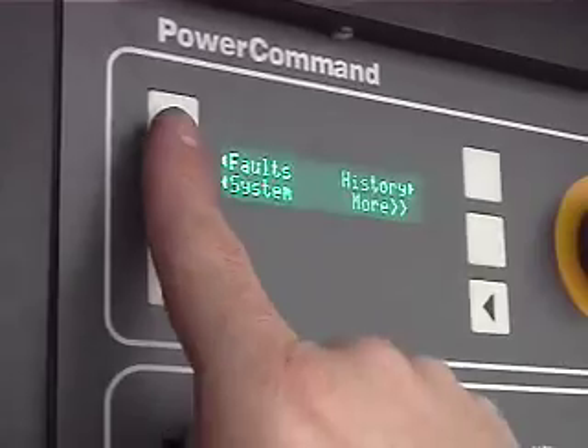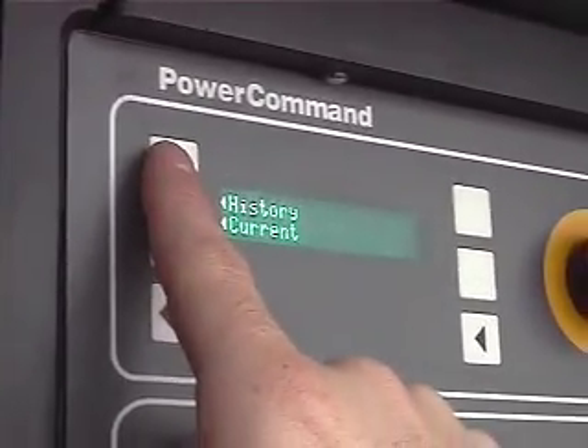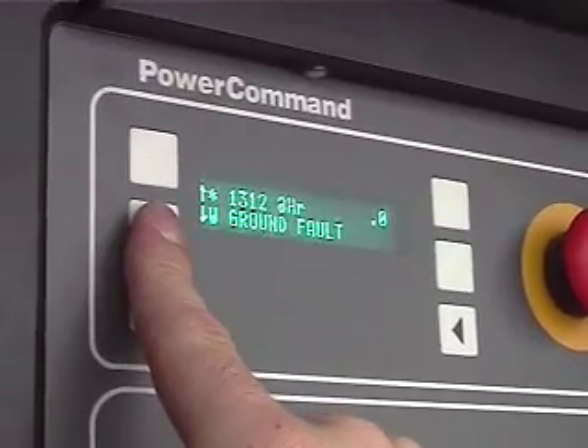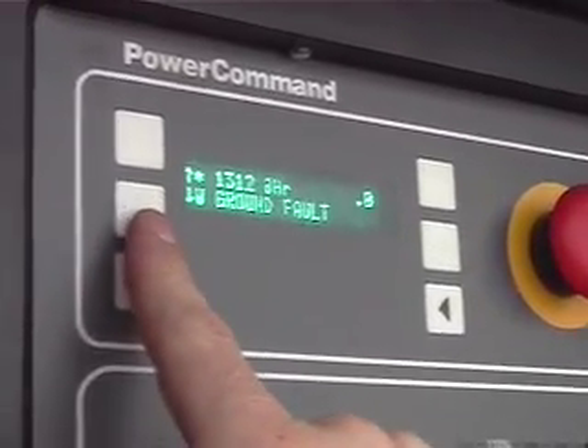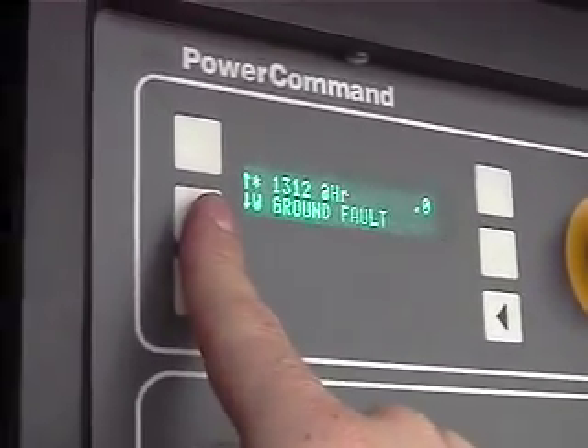If I go to more, the top one's faults. We can go into the history and see when faults have occurred. Now, how a fault is recognized is it gives you a fault code, it gives you a fault name, and then it gives you the control hours that the fault occurred at. That's one of the nice features with this control: it tells you pretty much down to within 6 minutes of when a fault happened.